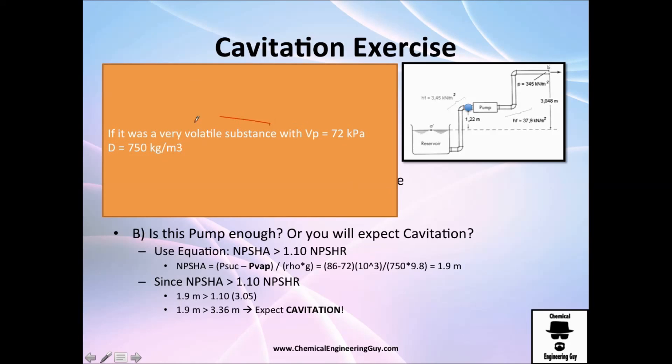Now, what will happen if you have very volatile substance? It is very low density and very high on vapor pressure, which means it'll vaporize very easily. Once again, we only change vapor pressure and density. The suction line is still constant, so 86 minus 72 times 1000 of the kilopascal divided by gravity and its density, which is 750. I got 1.9 meters.